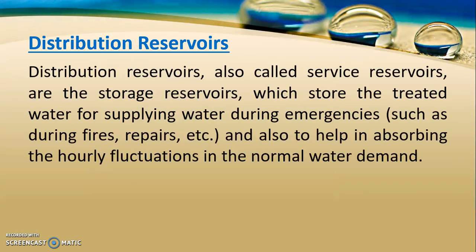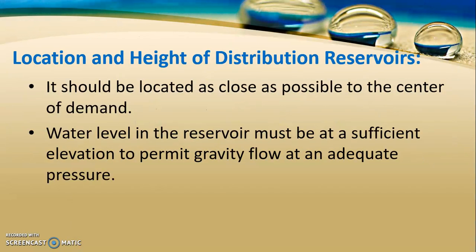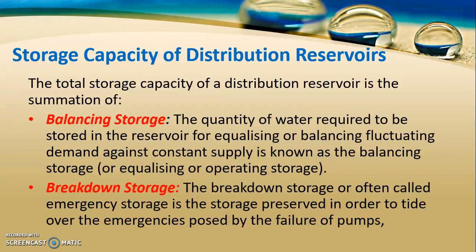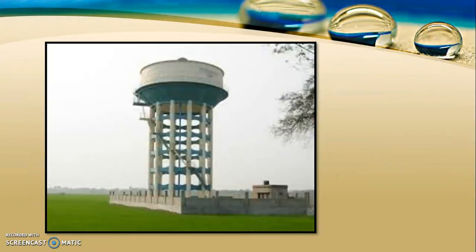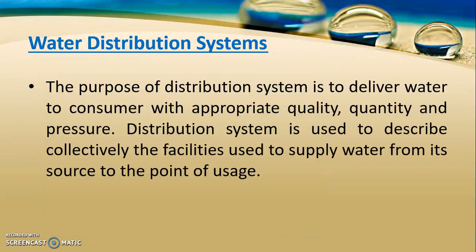After disinfection, the water is passed to distribution reservoirs used for storing the treated water. These reservoirs should be located near the center of demand and at sufficient elevation to permit gravity flow at adequate pressure. They should provide balancing against fluctuating demand versus constant supply, and should be able to provide water in case of pump failure or during fire outbreaks. You must have seen these elevated service reservoirs in your areas. After storage, the water is passed to the distribution system, from where it comes to your homes.